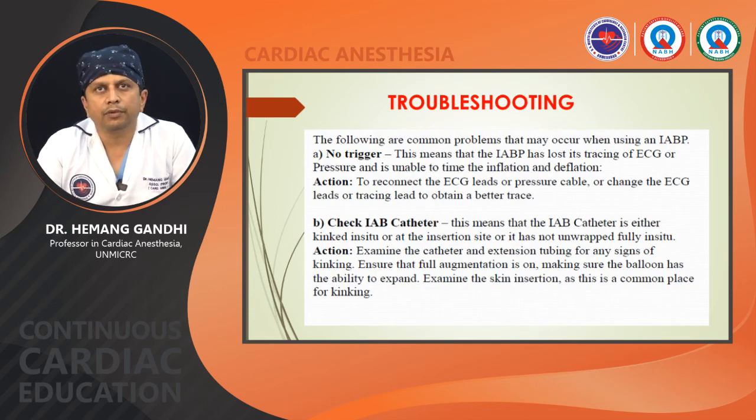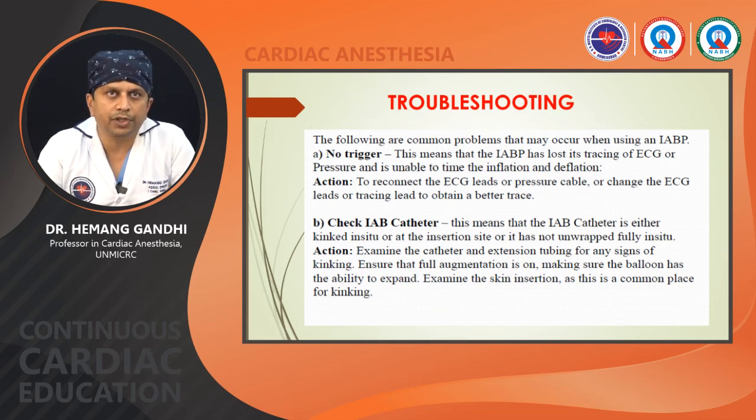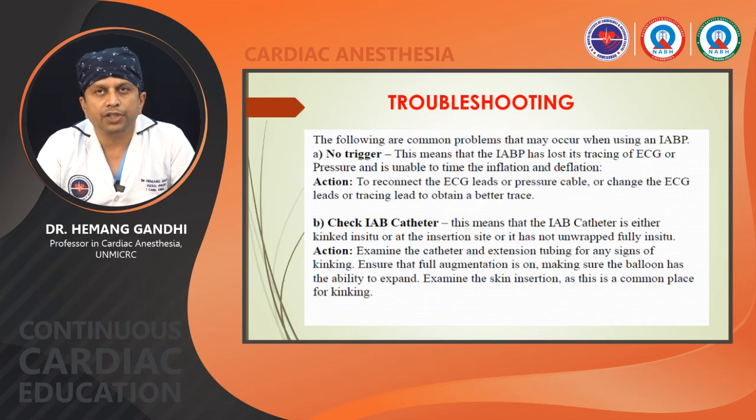This balloon has some issues which display on the monitor due to some troubleshooting, like no trigger. Why this no trigger? What do you mean by this no trigger? This means that the IABP has lost its triggering of ECG or pressure and is unable to time the inflation and deflation of the balloon.